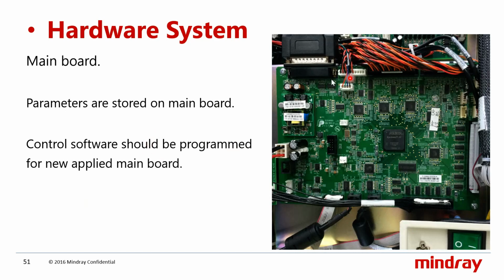So this is the main PCB. All the parameters are stored on the main board. Parameter means alignments. All the alignment files, everything will be stored in the main board. So control software should be programmed for a newly applied main board. Whenever you are replacing this main board, you need to always take a backup of the parameters. Store the parameters, and after replacing the board, there is a procedure. You have to restore the parameters.